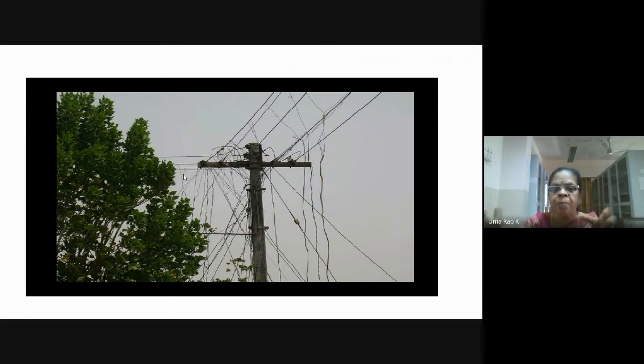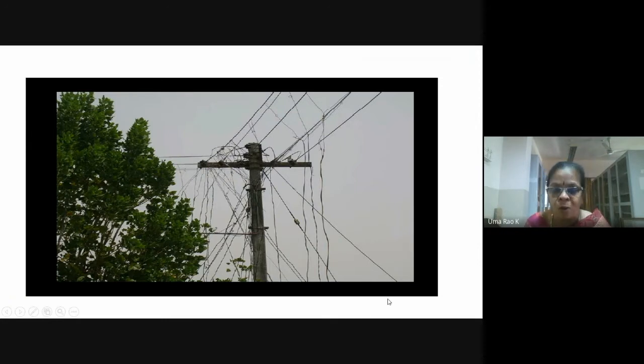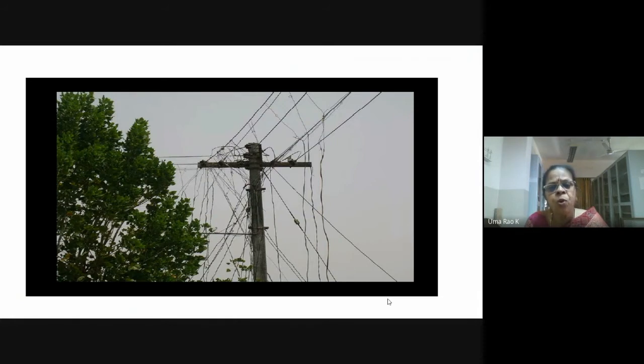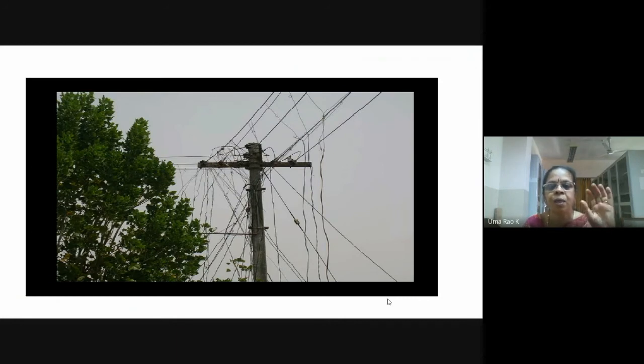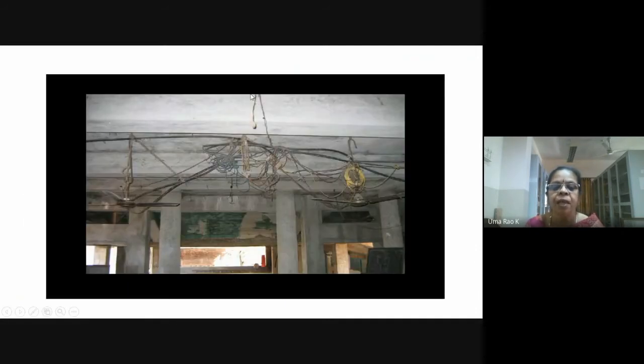When a tree branch bridges two lines it is like putting a conductor between them — you are short-circuiting the lines. You can have a line-to-line fault or a single line-to-ground fault through the tree. We know how harmful these unbalanced faults are — they cause huge currents and a lot of voltage unbalance. There are incidents of major blackouts worldwide that, when traced to the root cause, come down to not cutting trees.